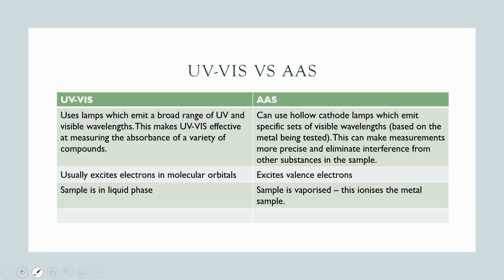Whereas with AAS, we use a particular lamp called a hollow cathode lamp. And these are made with different metal electrodes. So for example, if you were trying to measure the concentration of copper in a sample, you'd put in a copper hollow cathode lamp. And what's really special about that is the lamp can emit the exact wavelengths of light that the copper sample is actually going to absorb. And because you're not trying to emit a wide range of different wavelengths, it actually makes AAS a little bit more accurate.